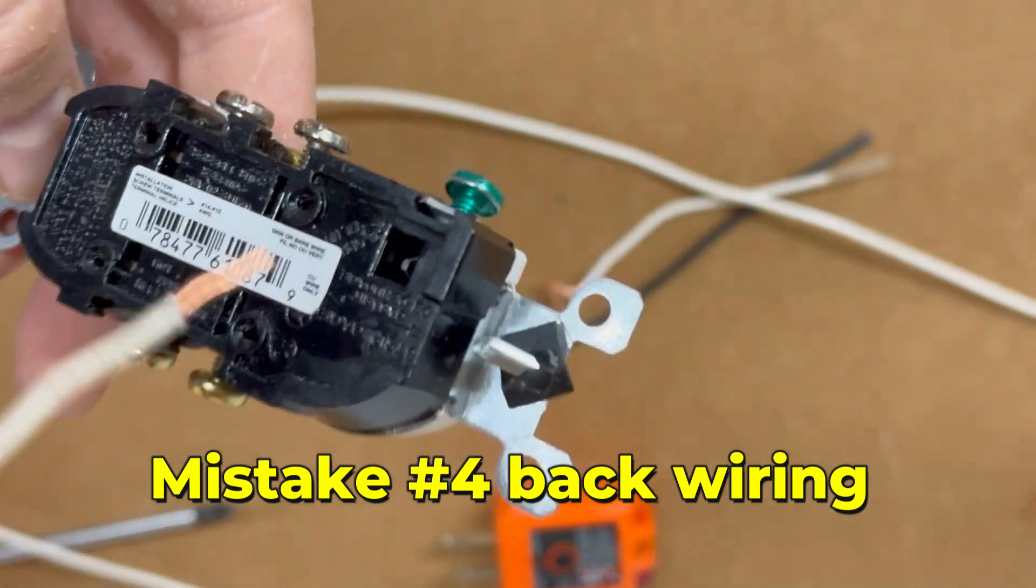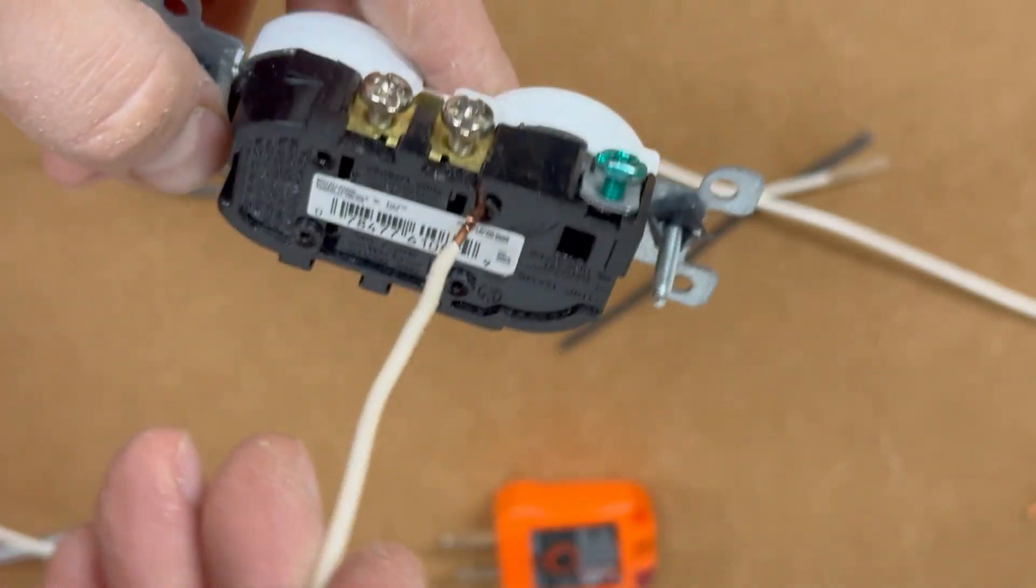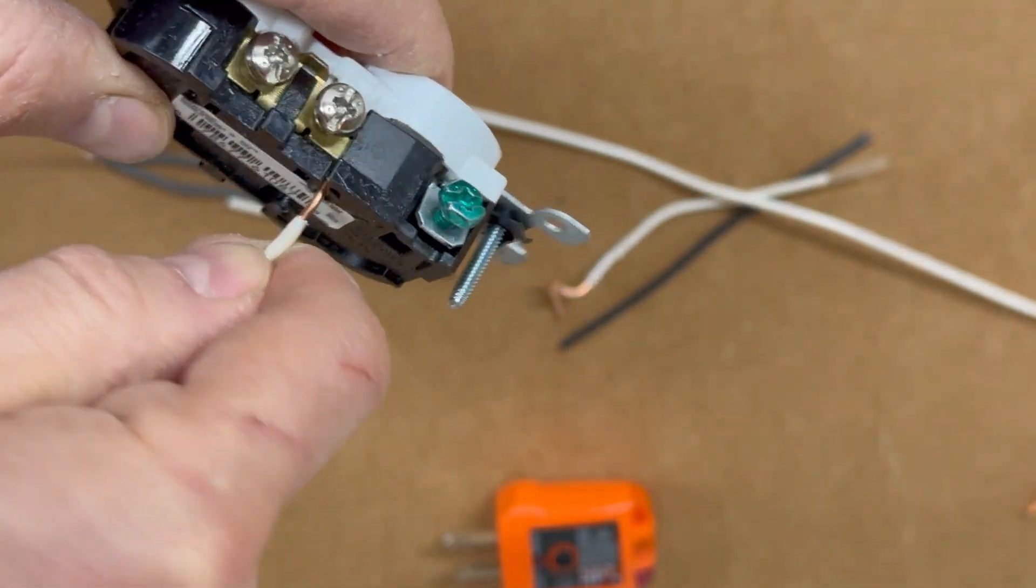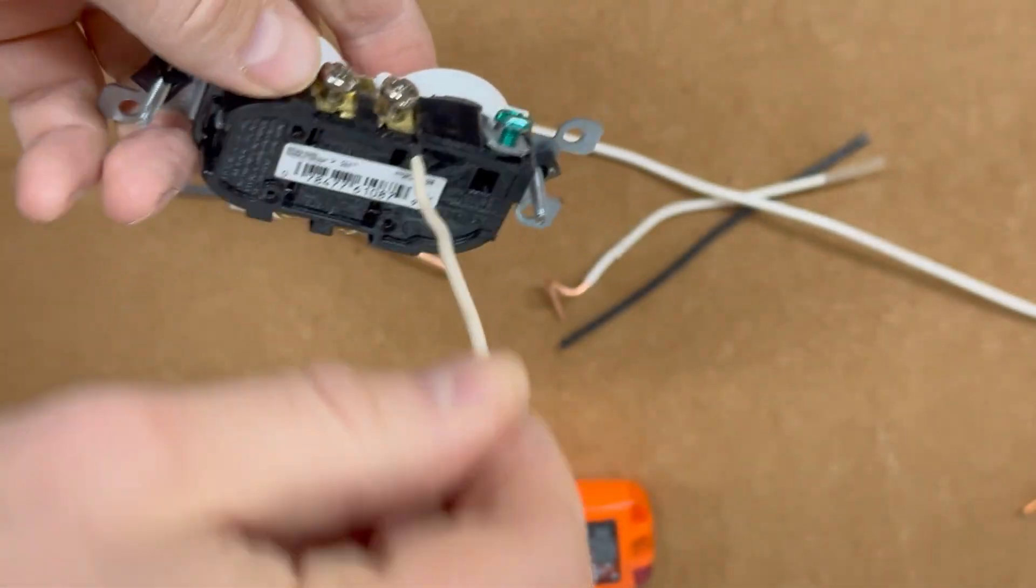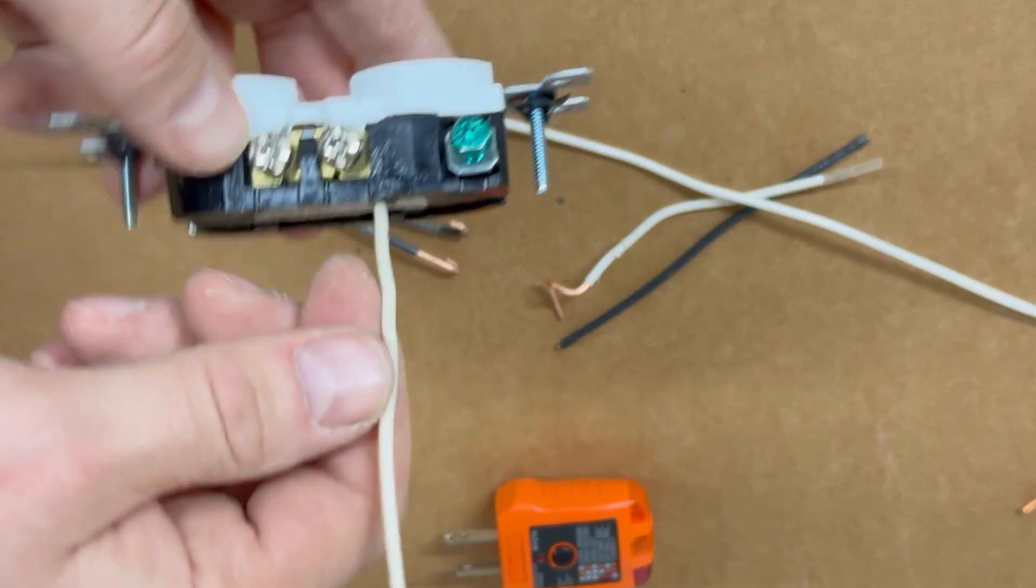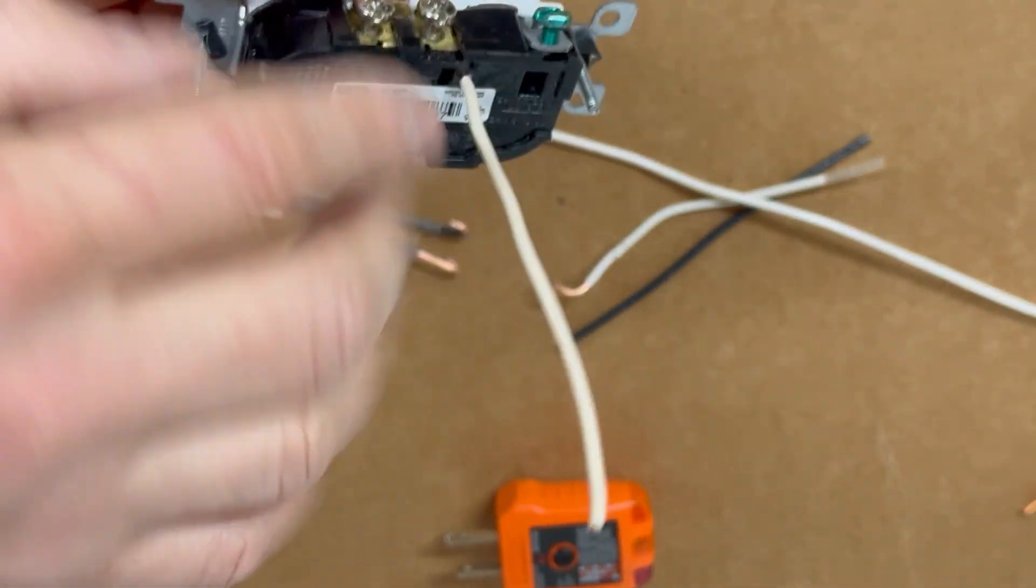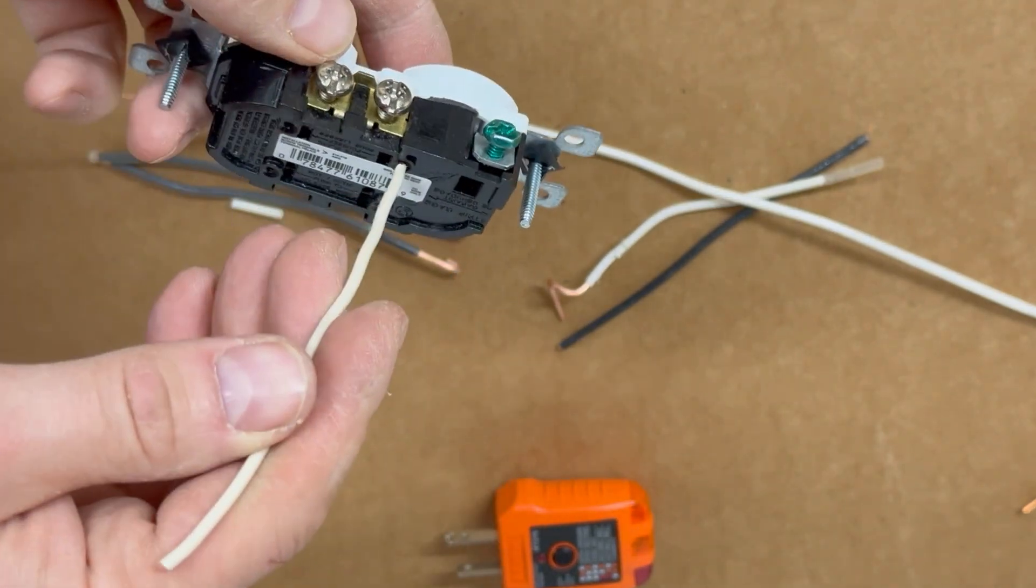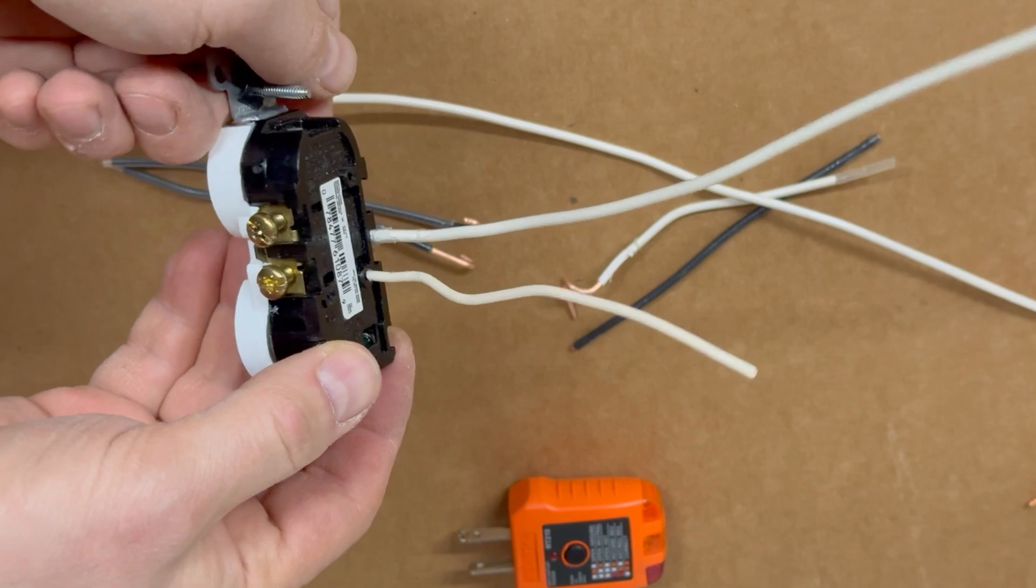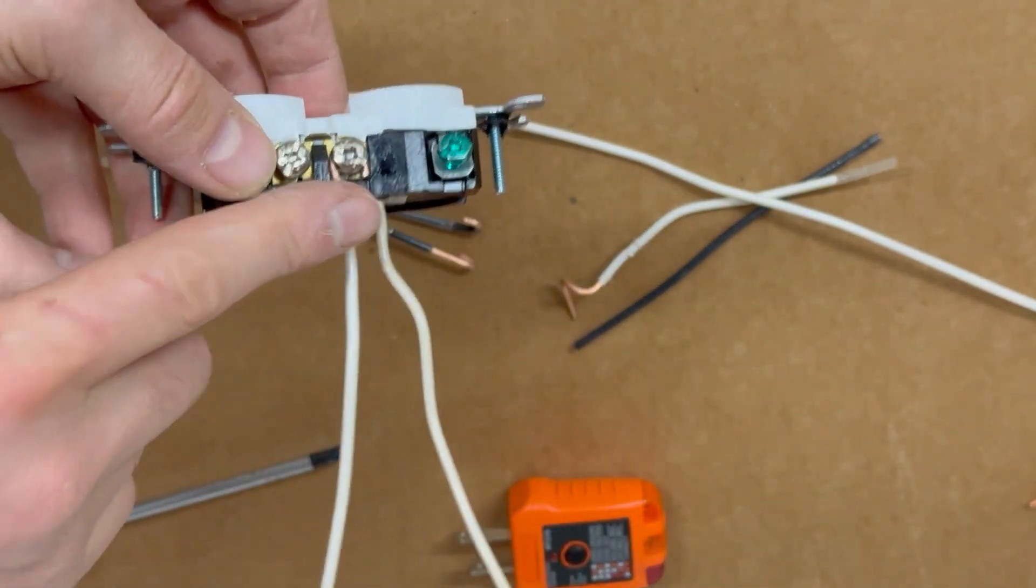Mistake number four: backstab wiring holes. Many 15-amp outlets come with small holes in the back designed for connecting wires. You just need to strip the wire and insert it into these holes for an instant connection. However, you should never use this type of connection. While it may seem convenient, it doesn't provide a reliable or durable connection. The wire inside the outlet doesn't make significant contact with the metal, especially for heavy-duty use.